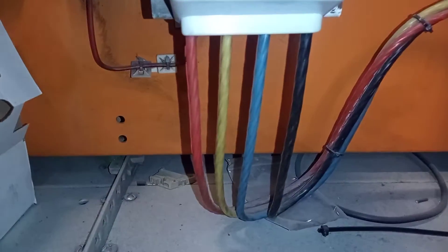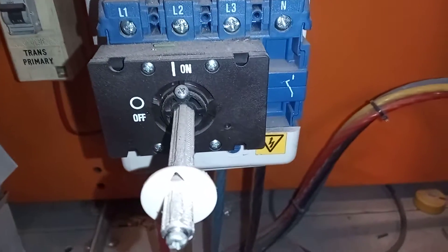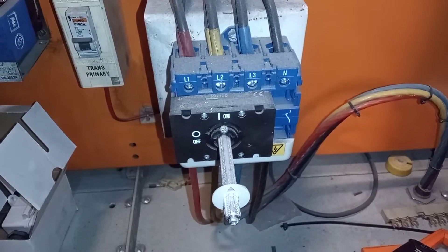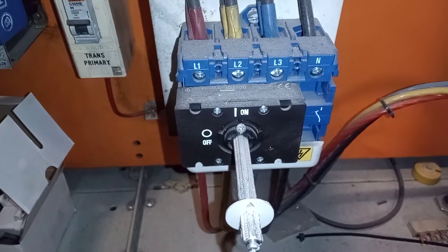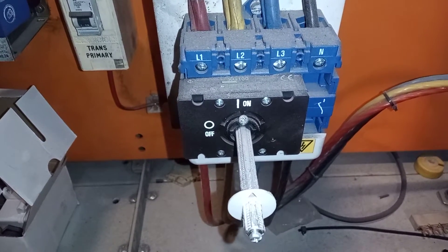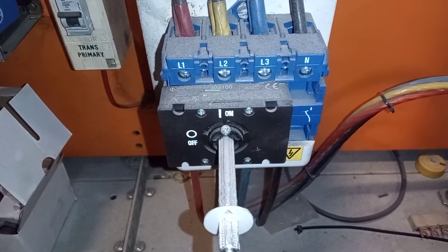We have our incoming supply down here — Live 1, Live 2, Live 3. There are at least two ways you can check: you can check phase to phase, so Live 1 to Live 2, Live 2 to Live 3, Live 1 to Live 3, or you can check from Neutral to Live 1, Neutral to Live 2, Neutral to Live 3.